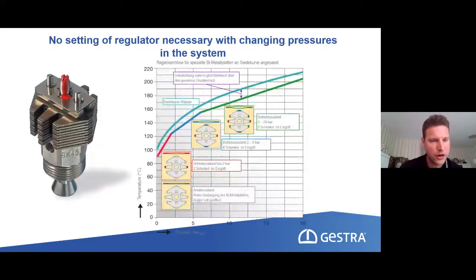So this is what an all-new bimetallic regulator or controller looks like. They have a red color on the top. That tells us this is the standard version of a bimetallic controller, because this is set to 20 Kelvin subcooling. We produce them in a room that is temperature controlled all the time, so that we can do it very, very precisely.